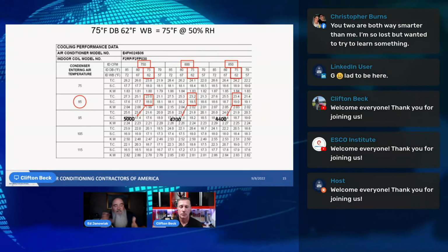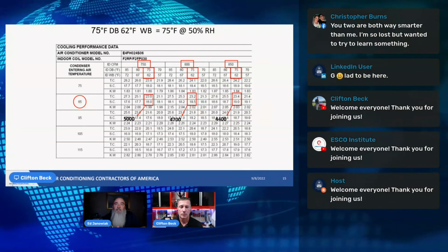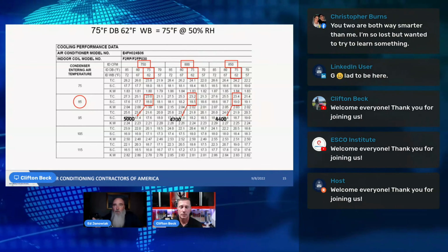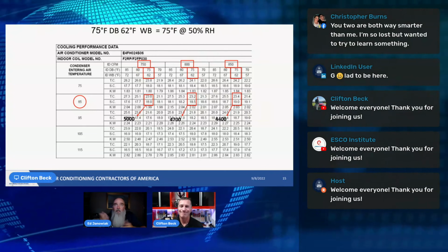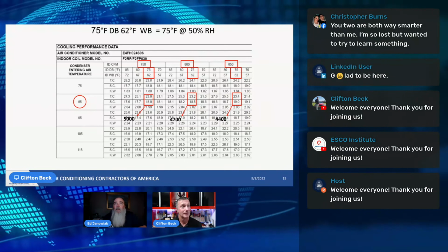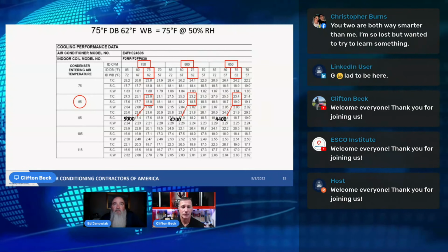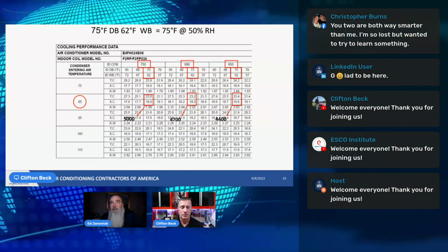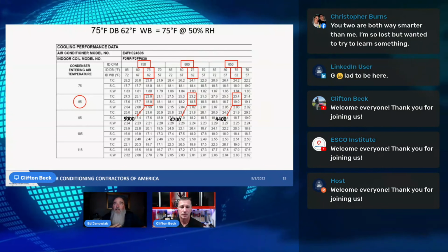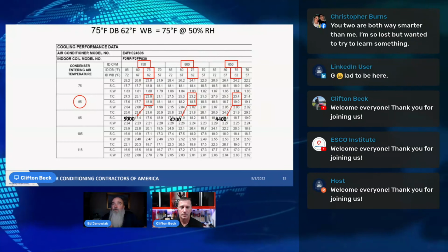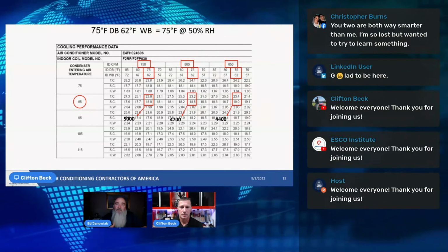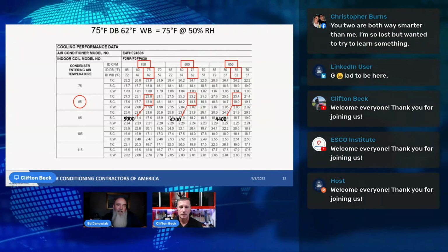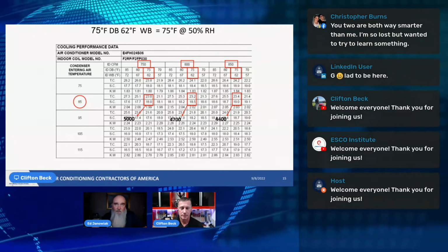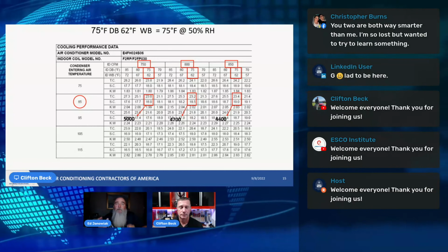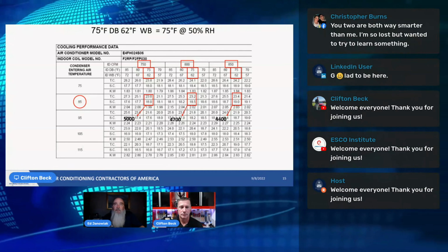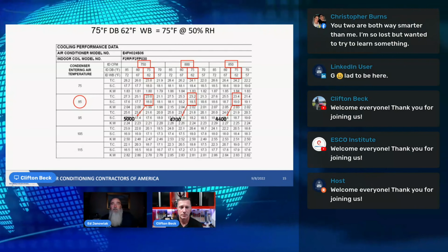We've been dancing around, so to speak, expanded performance data. We spoke about what happens to equipment performance as we slow the air down. If you look all the way to the right, the top box says 850. To your left, 800. To your left, 750. That's the manufacturer telling us what a 024 and an 030 match together. That's a nominal 2-ton outdoor unit matched with a nominal 2.5-ton coil together at 75 degrees at 50% relative humidity in the expanded performance data.